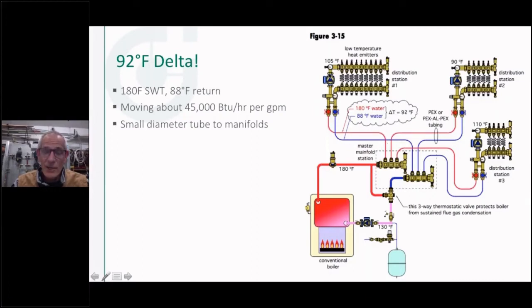I'm taking 180 degrees out here. I'm mixing it with my return water coming back at say 88 degrees, and that's how I'm getting that wide delta T. So now there's a system where I'm really leveraging wide delta T. I'm using small pipe, I'm using small pumps, because I'm leveraging that 180 to 88 degree delta T. Now that being said, I've got a boiler that's not going to condense, obviously, at those kinds of operating conditions. So a little give and take here.